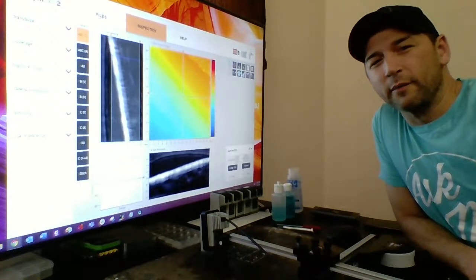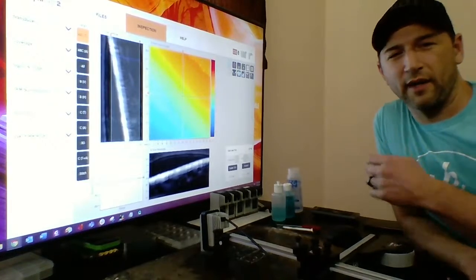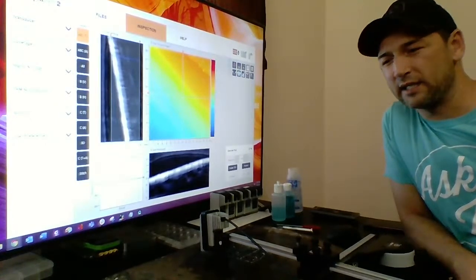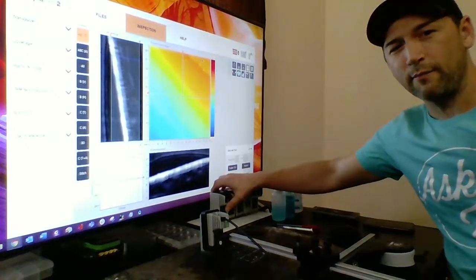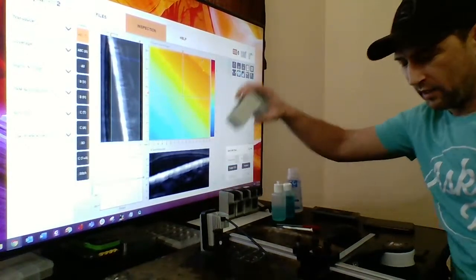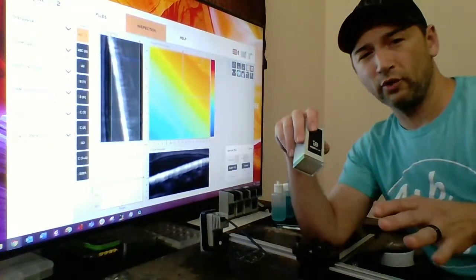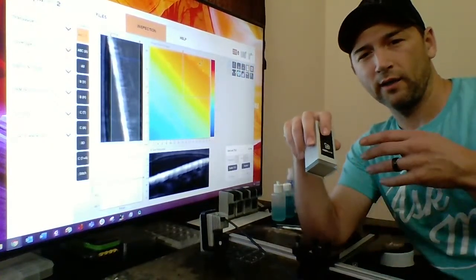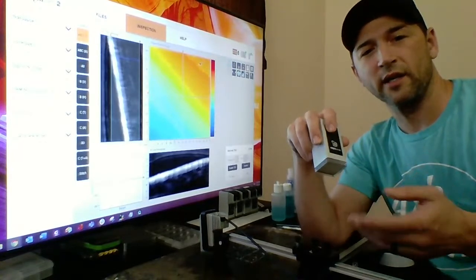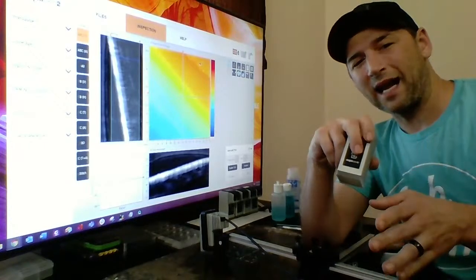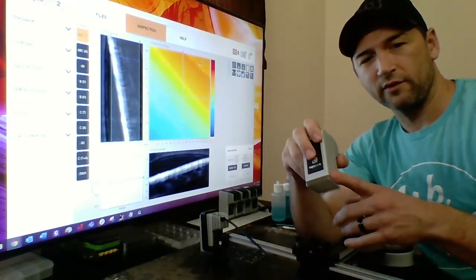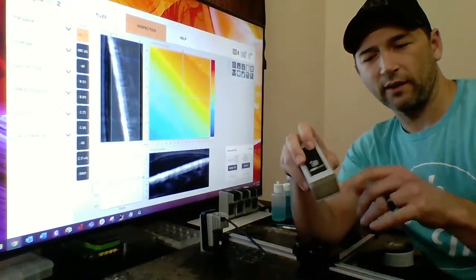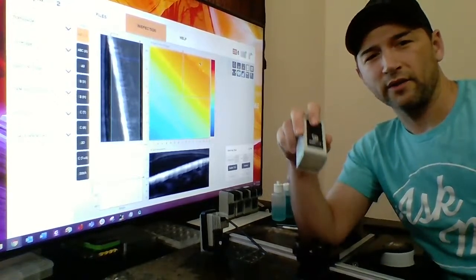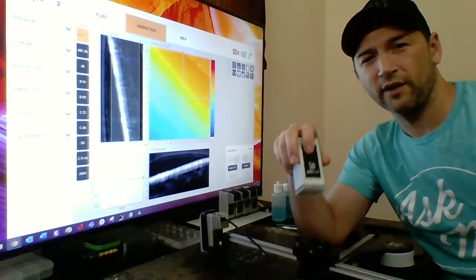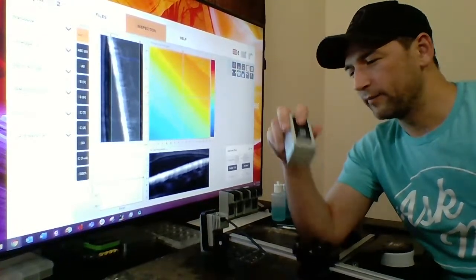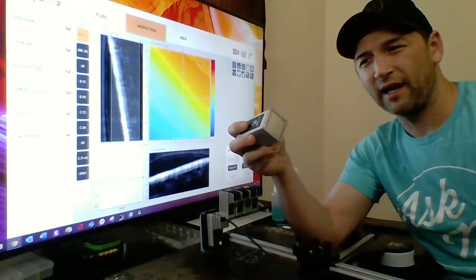If you're unfamiliar with the dolphicam, I'd like to start off by explaining a little bit about the dolphicam and its capabilities. The dolphicam is a 2D matrix array ultrasound system. It's capable of longitudinal beam only, so it's very much like a thickness tester, but has very high resolution. The transducer you see here is a 128 by 128 element transducer. It provides 16,384 active elements. So you heard me correct, 16,384 active elements.